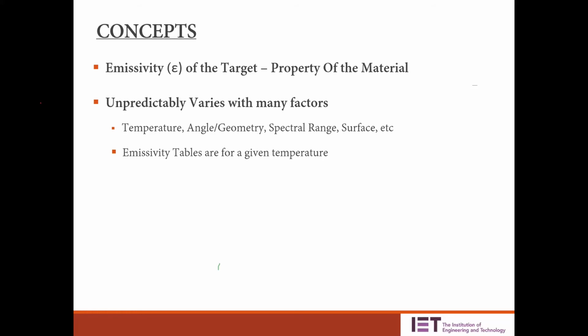The emissivity also varies with temperature itself. These emissivity tables are always given for a certain temperature, probably room temperature at about 26 degrees Celsius. When the target temperature increases, say to 100 or 200 degrees, the emissivity decreases. So if you are trying to measure the target temperature at 200 degrees, your emissivity table value is no longer valid.